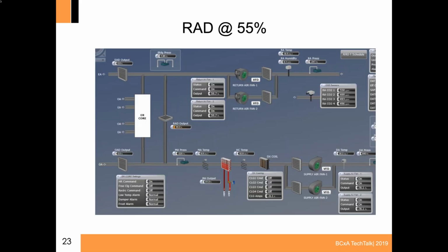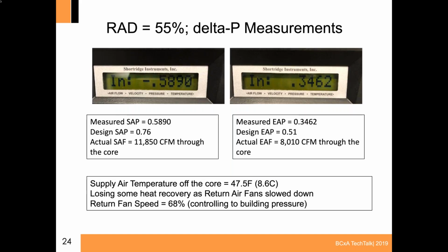So we lowered it to 55%. The mixed air temperature increased. The return fans continued to decrease down to just under 60%. And our results now, we were getting much closer to the design, 11,850 across the core with that measured pressure drop. And we were up to 8,010 CFM, which is now above the minimum amount.